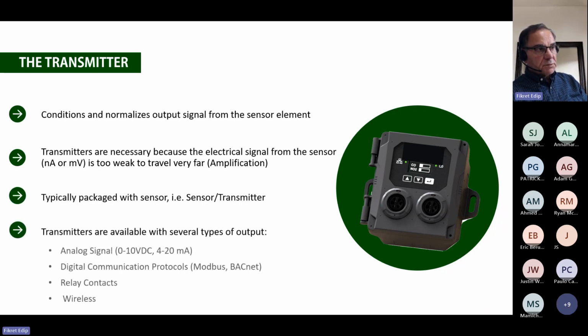Transmitters are available in a variety of types. A gas detection manufacturer can give you a signal out of 0 to 10 volt or 4 to 20 milliamp, or digital communication over BACnet, and often they have a built-in relay contact. And now a lot of gas detection manufacturers are aiming for wireless. It is not widely available right now, but it will be as the technology progresses. When you have wireless, obviously you will be eliminating the wires and conduits in that premises.